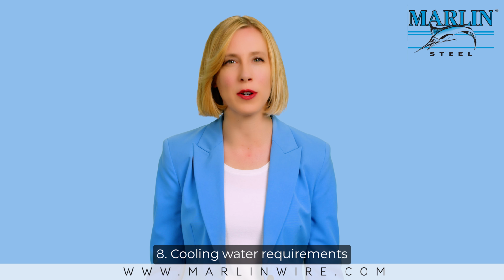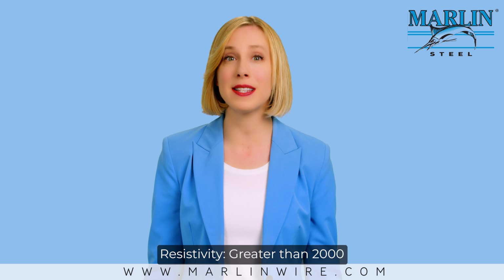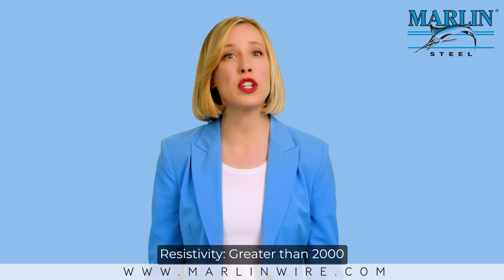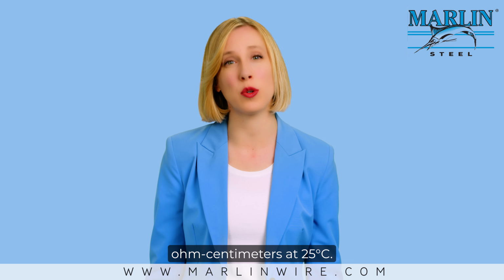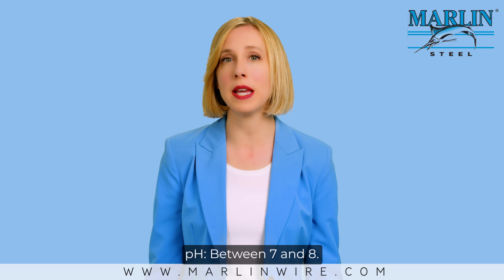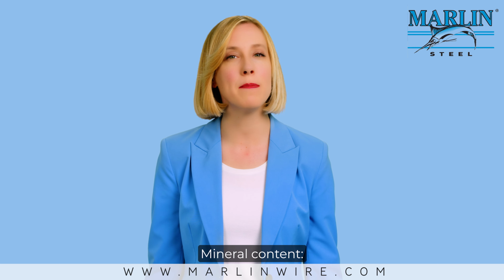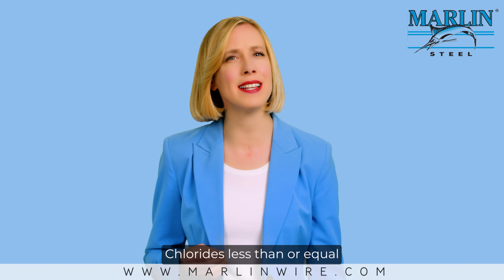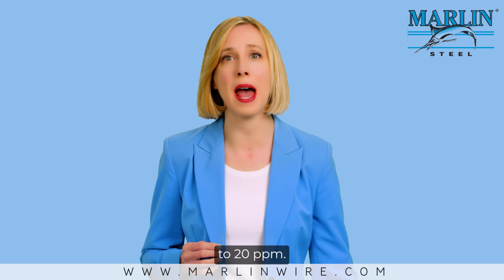8. Cooling water requirements. Resistivity: greater than 2,000 ohm centimeters at 25 degrees Celsius. pH between 7 and 8. Mineral content, chlorides less than or equal to 20 ppm.